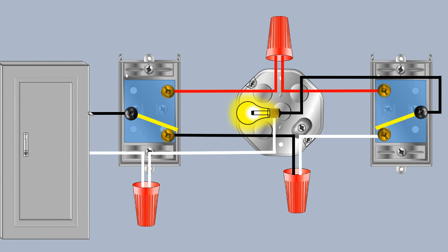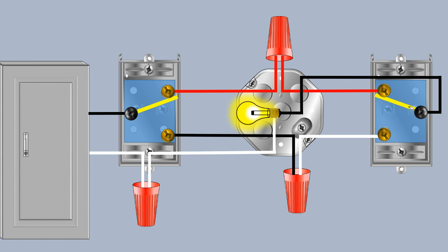Following the path for current: it comes from our line through our first three-way switch, down our traveler, spliced inside the wire connector, continuing on the white conductor — which is acting as a traveler — through the paddle to the black common screw, then back to the light on the switch leg, and back on the identified neutral conductor to the panel, completing the path with the light on. If we flip the second switch to the up position, that path is broken and the light goes off. Flipping the first switch back up re-establishes the path through the red traveler, back to the light on the switch leg, completing the circuit again.